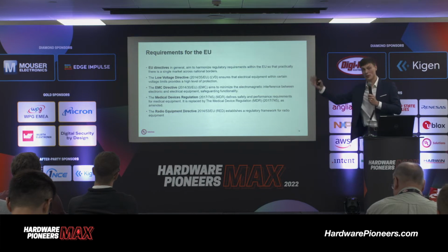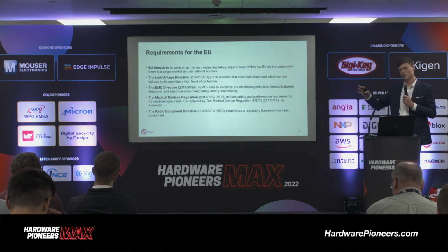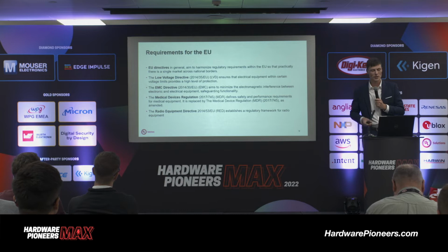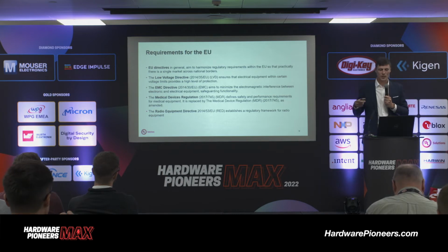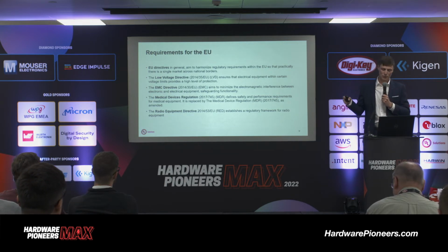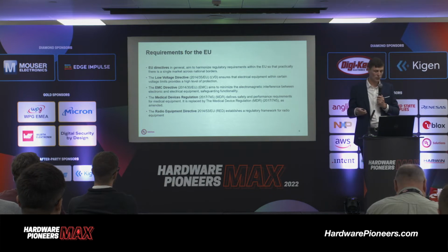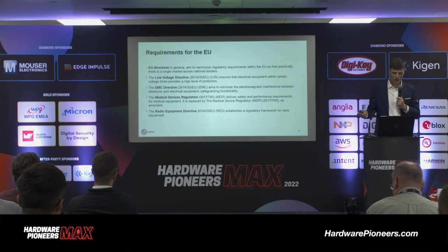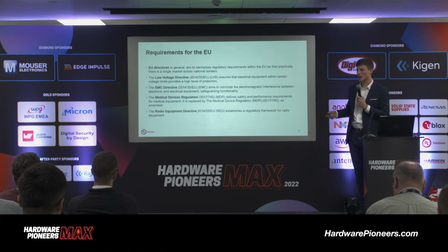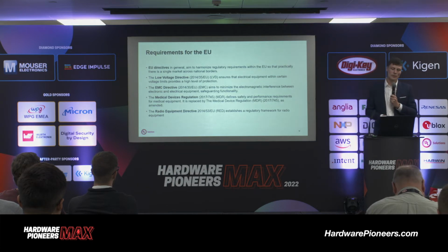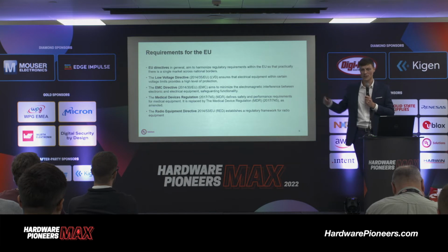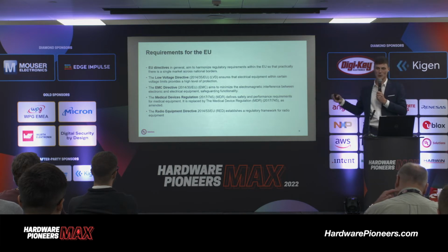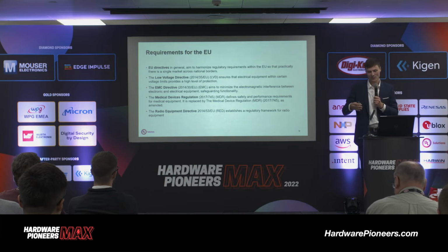Of course, if you're working in the machinery world, or if you're in hazardous locations, things are a little bit different. But in terms of consumer and medical, you'd be looking at the low voltage directive, otherwise known as the LVD, which typically would apply to devices between 50 and 1,000 volts for AC, or 75 and 1,500 for DC. The EMC directive, which would be applied to any active electronic device, considering its emissions profile, so how much noise does it kick out into the rest of the world, or its immunity profile, which is how much noise can you fire at it without it malfunctioning. And every device is considered in this context when you're looking at EMC.